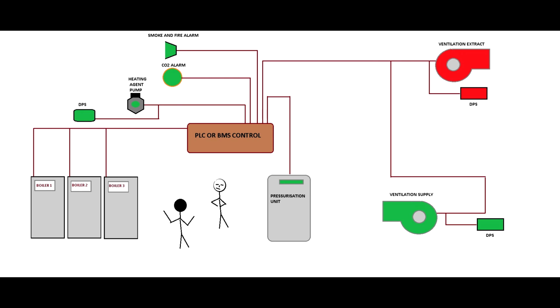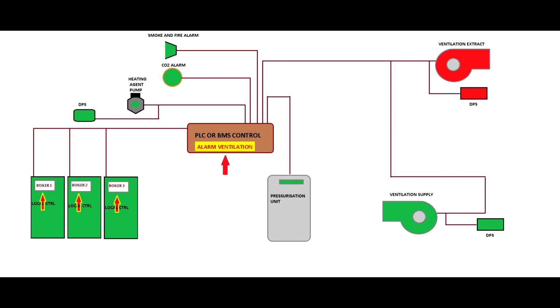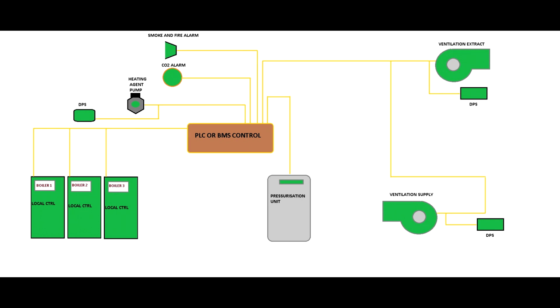And I told the manager I can't turn them on because I have a faulty fan. But the manager spoke to one of my colleagues, a respected gas engineer, and my colleague spoke to the boiler company on the phone, and he managed to manipulate the local control and the LMU to change its settings, and the boilers started running on a local controller. So the boilers ignored the fact that the PLC was asking for them to be off because of the faulty extractor fan. So I have a ventilation problem. And then he was a hero because he heated up the store without ventilation in the plant room, which is practically illegal. He breached the HAC rules.